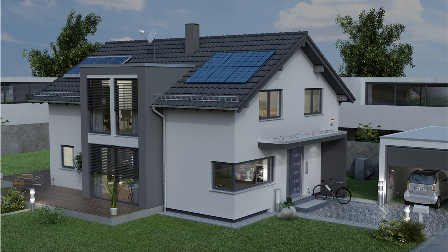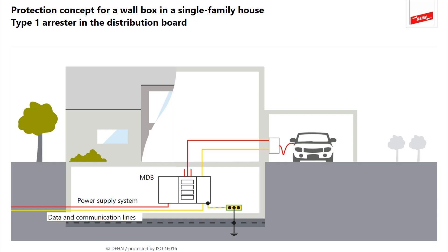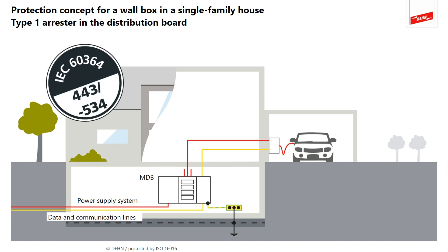You are planning to install a wallbox. What do you need to think about when building a new single-family house or retrofitting? Surge protection in residential buildings is mandatory in Germany. The IEC 60364-4-44 clause 443 and IEC 60364-5-53 clause 534 standards require protection measures in the main distribution board. The protective devices must be installed as close as possible to the origin of the electrical installation. It is common practice to install a type 1 arrestor upstream of the meter. The data and communication lines are also protected to ensure a permanently effective protection concept — type 1 arresters are also used here.